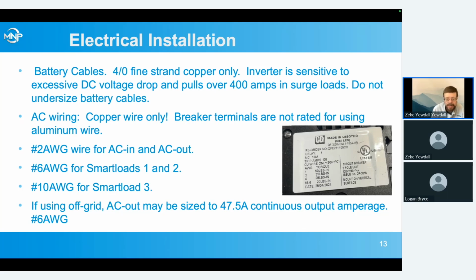On the AC wiring, the breakers in this inverter are only rated for copper wire. This is a picture of the sticker on the side of one of those 100 amp input breakers, and you can see it says copper wire only. So I know everyone wants to run SER cable to these, but that's not rated for that.